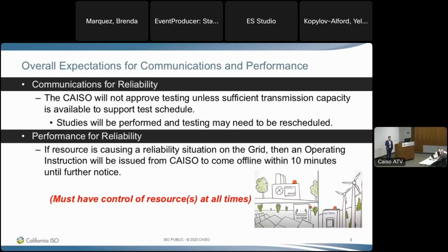And oftentimes what we'll see too, say that 100 megawatt BESS example, plus or minus 100 megawatts. You've got negative 100, positive 100, so a 200 megawatt delta there. Sometimes what we'll see is they'll say, okay, I'm going to charge negative 100, and at the top of the hour I'm going to go to 100. Sometimes they'll just switch 200 megawatts right at the top of the hour. That can cause an issue.